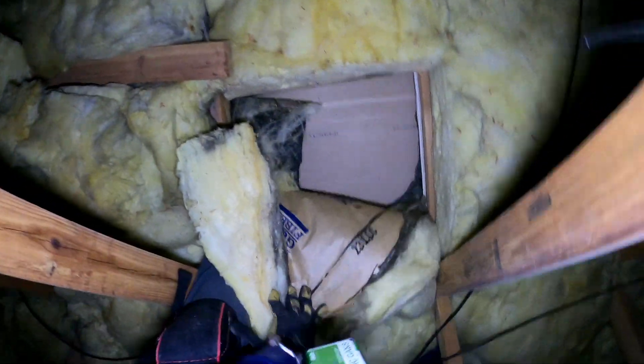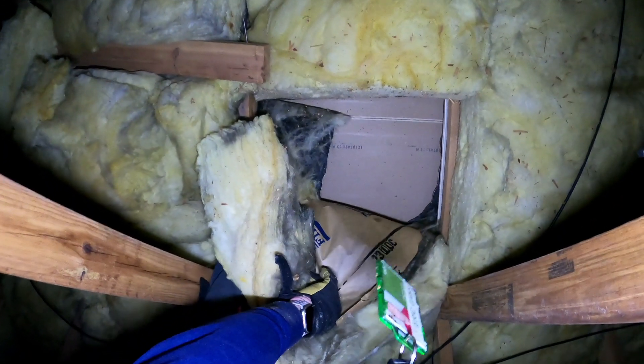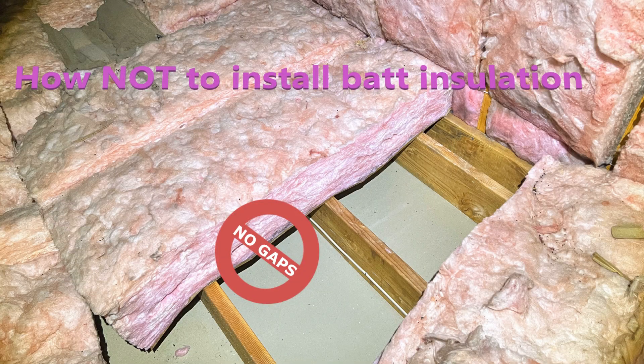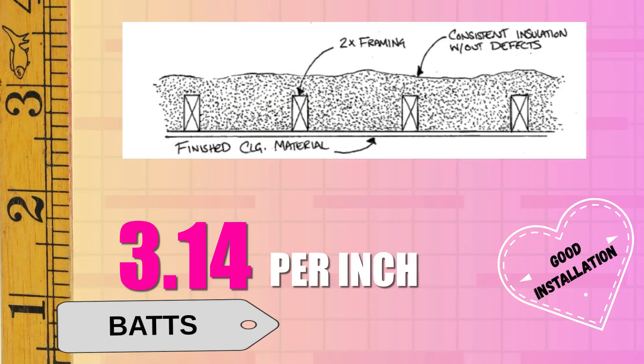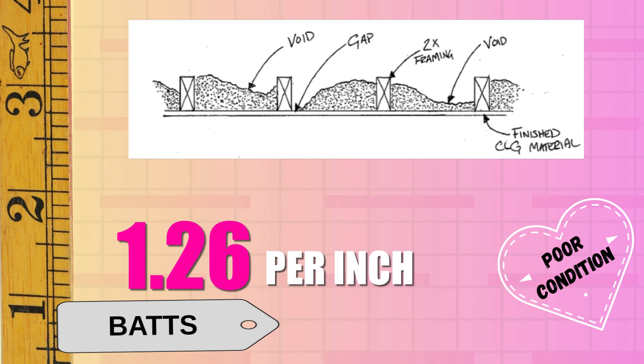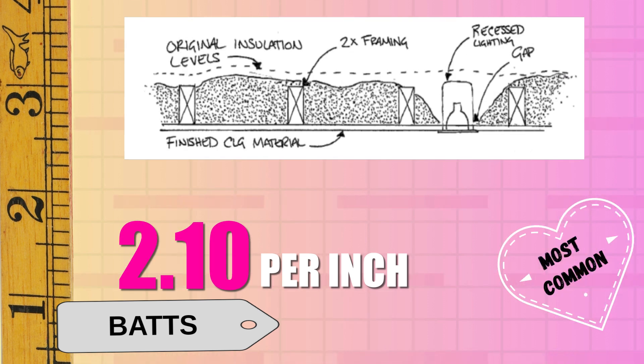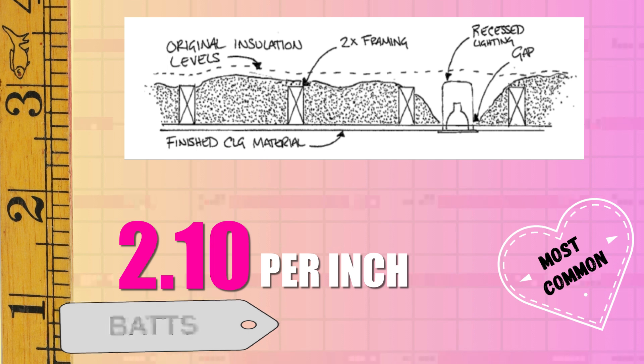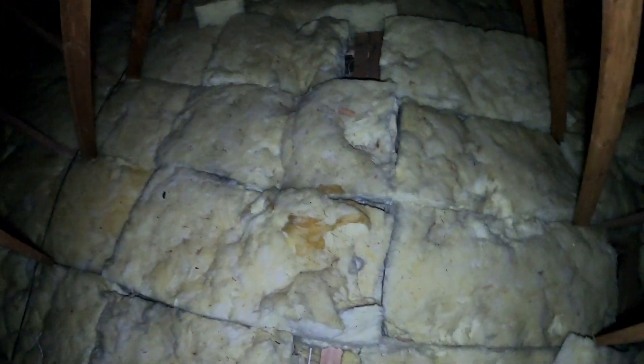Fiberglass batt insulation, famously marketed through Pink Panther commercials, features craft paper or aluminum foil backing on one side. While common, it requires meticulous installation as it is unforgiving of mistakes. New fiberglass batts provide 3.14 R-value per inch, but poor installation can significantly reduce effectiveness to as low as 1.26 R-value per inch. Most of the attics I visit with fiberglass batt insulation have an R-value of 2.1 per inch, so that is a safe number to use if you have moderate coverage, meaning the insulation is generally in good contact with the ceiling.